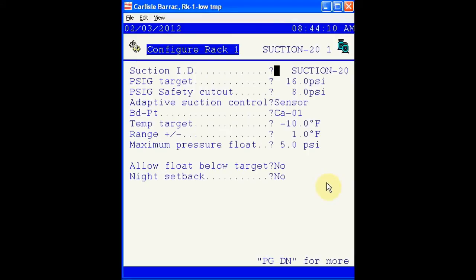In the suction info screen, we can see that floating is turned on. This particular rack is floating based on a board point. The board point in this case is a calculation. This calculation looks at a target temperature of -10 degrees Fahrenheit, plus or minus 1 degree. As you can see, it's important to know that the rack cannot float more than 5 pounds. As we saw before, that means this rack cannot float above 21 pounds psi.